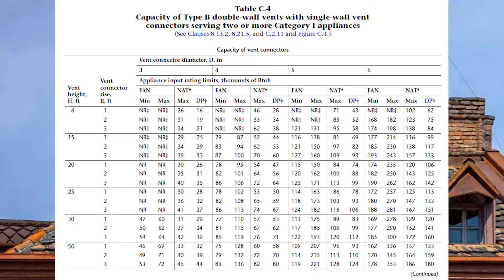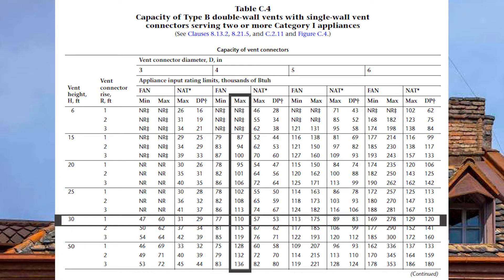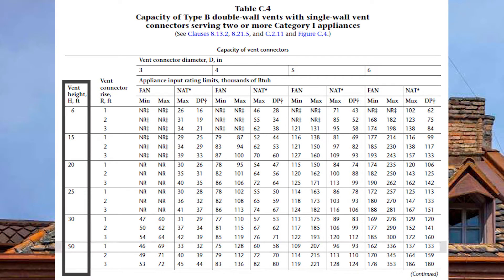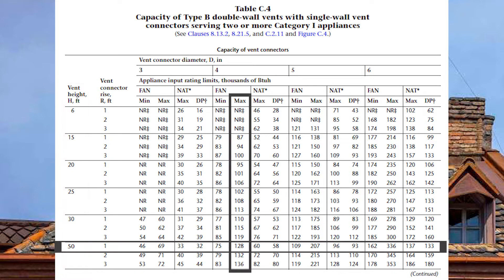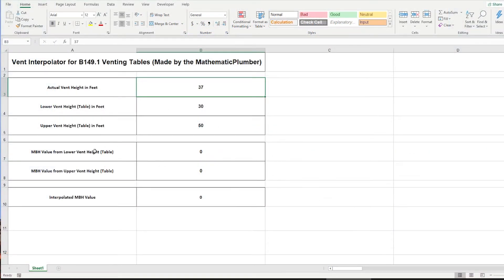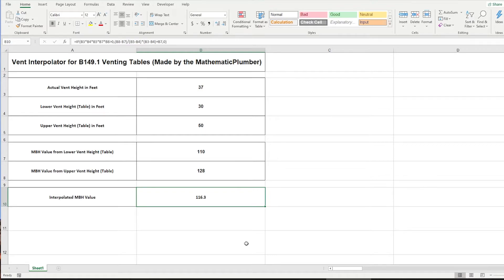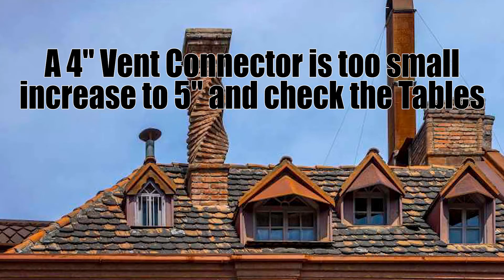Actual vent height is 37 feet, lower vent height 30 feet, upper vent height 50 feet. For the 120 MBH fan-assisted furnace, go down to the 30-foot vent height across on a 1-foot vent connector rise — 4 inch is good to 110 MBH, not quite enough but that's okay. At the 50-foot vent height with 1-foot rise, 4 inch is good to 128 MBH. Entering 110 and 128 into the calculator gives an interpolated value of 116.3 MBH — slightly too small, so we need to bump up the vent size by one.